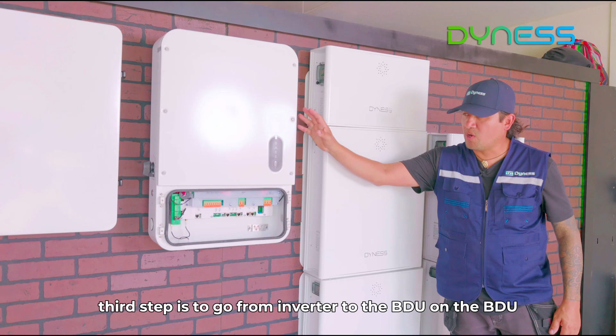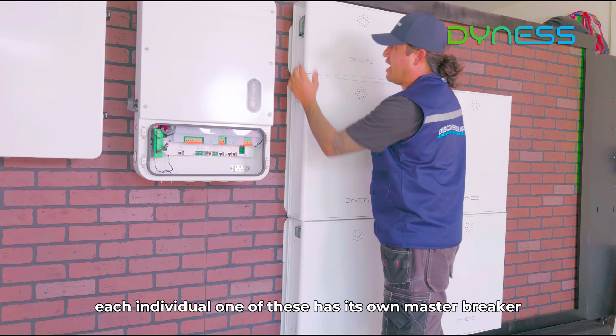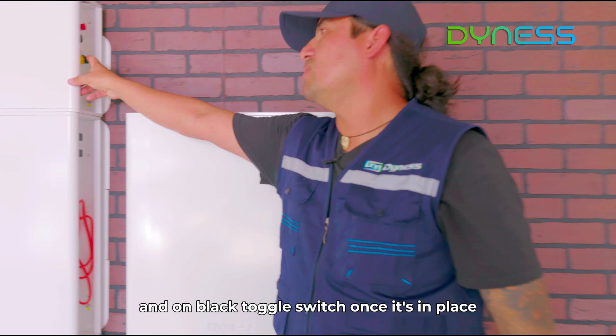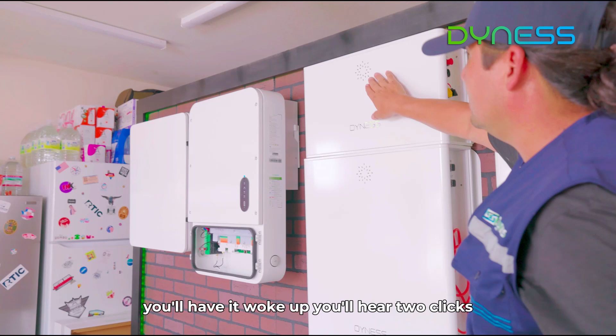Third step is go from inverter to the BDU. On the BDU, each individual one of these has its own master breaker. We need to have it in the up position. One here, one here, one here, here, and here. Once all in place, our next step is to wake it up and then do the off and on black toggle switch. Once it's in place, you'll have it woke up. You'll hear 2 clicks. You'll see the LED lights and all the individual batteries light up in blue.